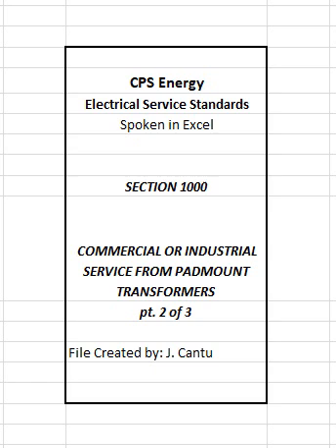11. Customer shall furnish single-barrel, 2-hole tongue lugs for termination of all conductors onto bus in tap box. Mounting holes in tongue to be 9/16 inches and vertically spaced 1 3/4 inches apart. Cable lug width shall not exceed 1 3/4 inches and height shall not exceed 2 1/4 inches. 12. Each lug used shall be plated to industry standards and shall be a type approved for the conductors and for connection to the bus bars. When all components are aluminum, bus and lugs, only aluminum bolts and washers should be used.